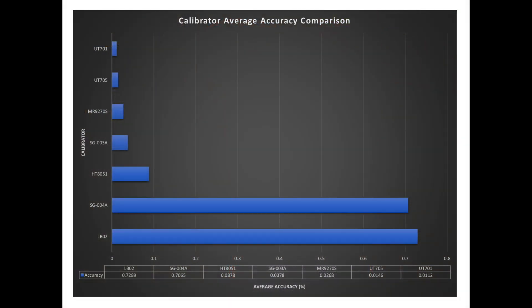We'll just put this plot here as well. This is a comparison of the average accuracy of all the calibrators that I've tested. The UT701 there, its average accuracy is better than anything else I've tested up to this point here. And you can see the UT705 is just below that. So that is a combination, seems to make quite a good pair. After that we've got the MR9270S, and of course that includes a lot more functionality than is offered by the UNI-T units. But it's very good performance really, all things considered.